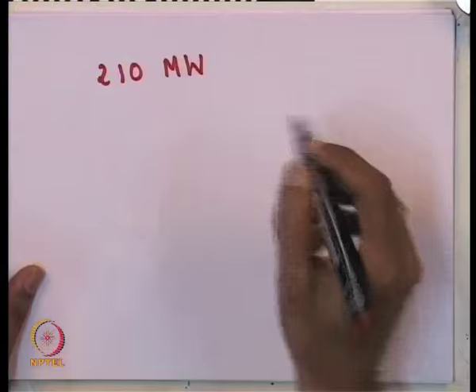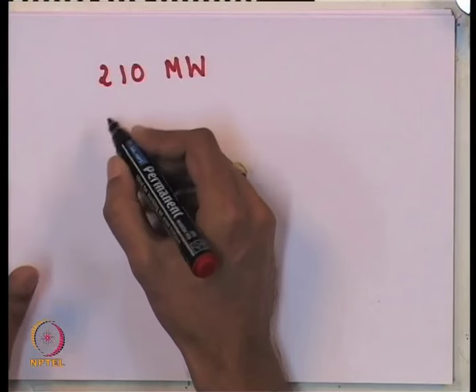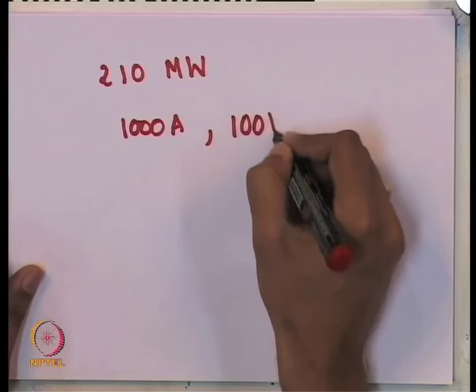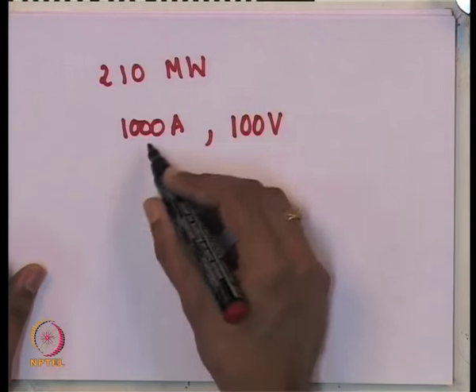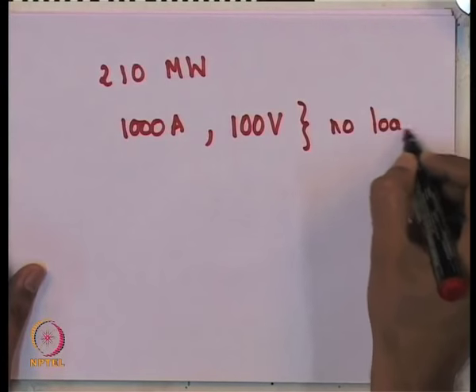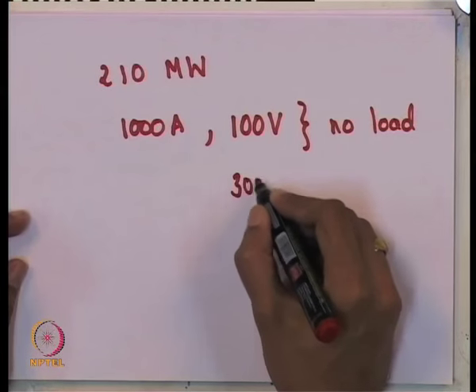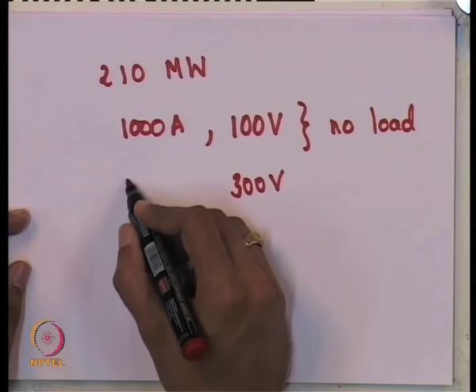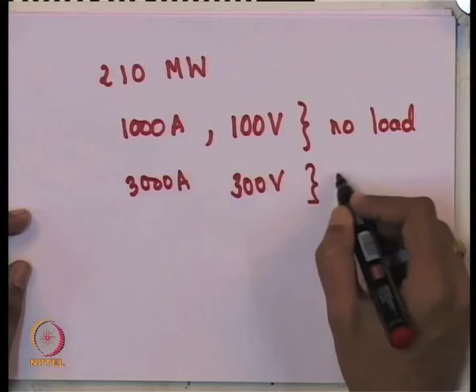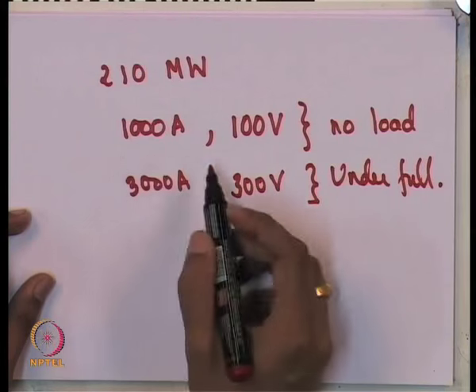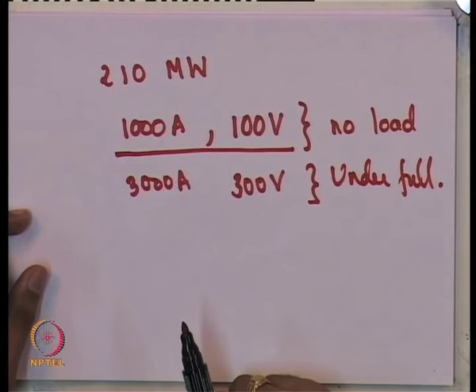For example, a typical 210 MW set under no-load conditions has excitation currents of approximately 1000 amperes and voltages of around 100 volts applied to the field winding. Under loaded conditions this may be three times as much — approximately 300 volts and 3000 amperes. The excitation power required is not very high; under no-load conditions it is less than a megawatt.